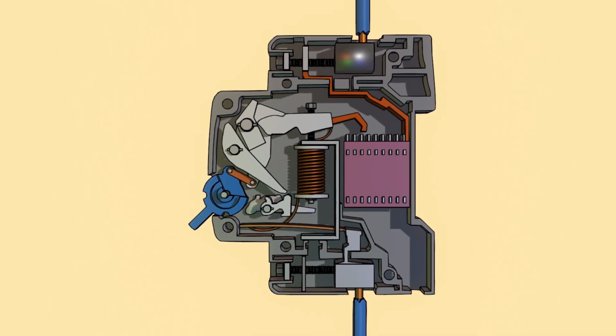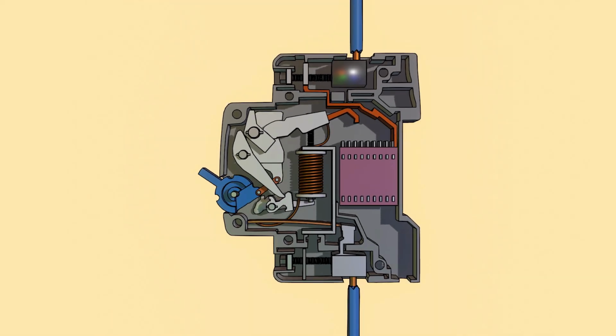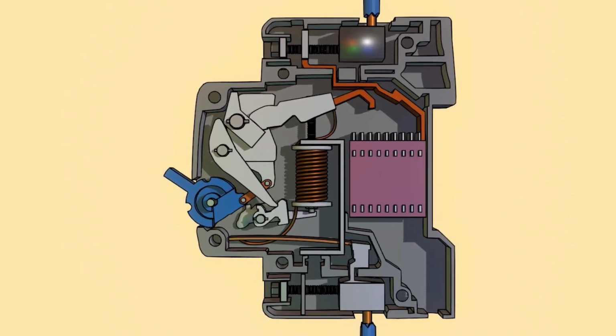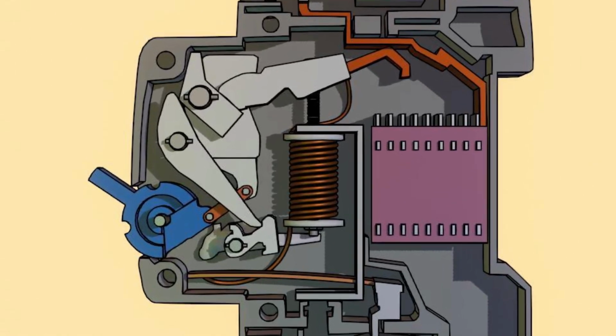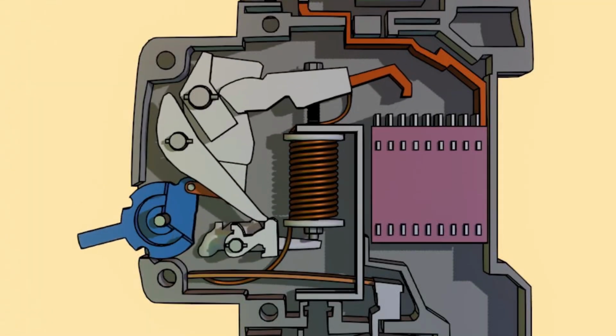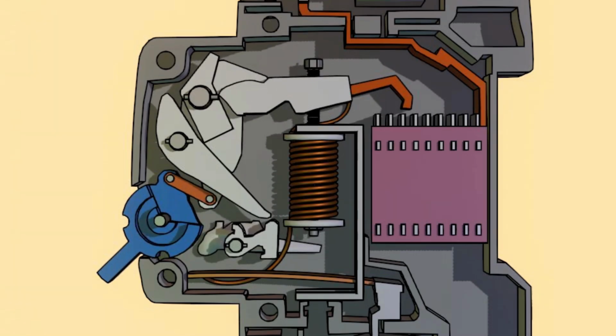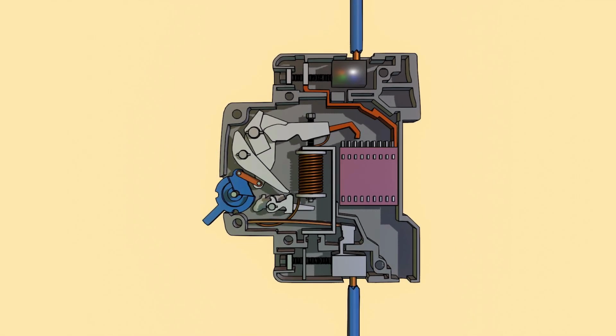Now suppose a short circuit occurs. The current in the circuit suddenly becomes very high. When normal current flows through the coil, it produces a magnetizing effect. But it is not sufficient to move the plunger. When the current exceeds the limit, the magnetic force increases sharply. The plunger moves down, pushes the mechanism, and releases the spring-loaded lever. The mechanism rotates, moving the contact away from the fixed contact, breaking the circuit during a short circuit fault.